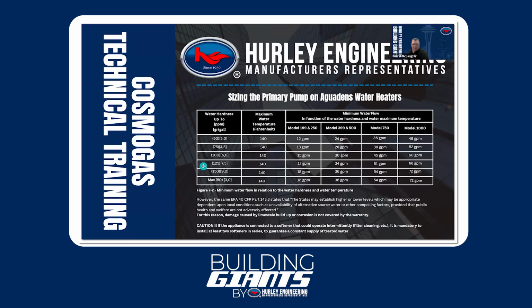Okay, so moving on here, we're going to get into some of how we size these. I'm going to try not to be too detailed, but I'm going to try and hit the high points for how we size these pumps and keep the flow accurate so that we don't scale up the equipment. This chart is in all of the manuals that come with CosmoGas equipment. And you can see starting out over here, they've got a water hardness. So my first number here is going to be my parts per million of water hardness. And the second number is grains per gallon, depending on what number you typically get with your reports.